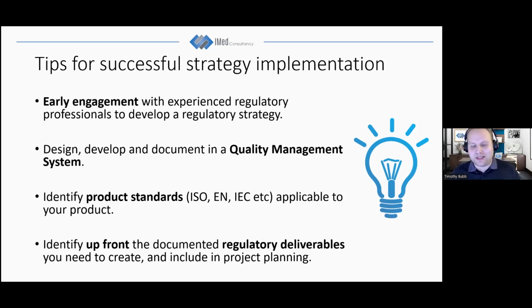Upfront, try and identify what product standards you need to meet. Within medical devices, the underlying technologies, particularly for electronic and physical products, are now quite well characterized in terms of the science. We know for a lot of products what that baseline level of safety is for particular product types. For example, a catheter may have particular requirements. A medical device which includes electronics that come into contact with the patient also has basic levels of safety set through standards. Regulators will generally expect you to meet those standards because they have assessed and determined that those standards meet their requirements in applying the regulations.